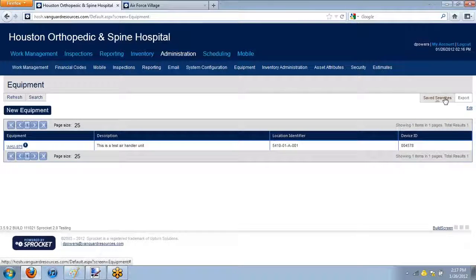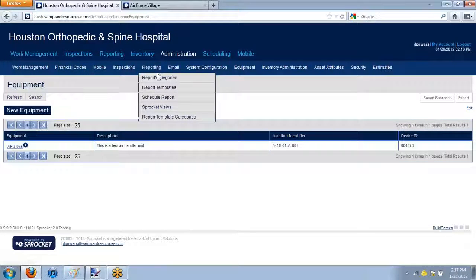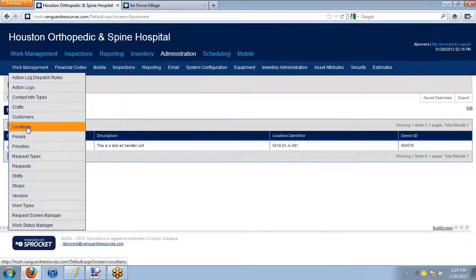Now, everyone should have their locations put in. They're different than what you're used to, and what Mary Lou's decided is she wanted to group them even further than how we've grouped them so far. The benefit of doing that is it's easier for you to find your pieces of equipment if you know the scheme that you want to do. So what I'm going to do now is, everyone's scheme has been building number, floor number, area, and then room. So I'm going to add another area.